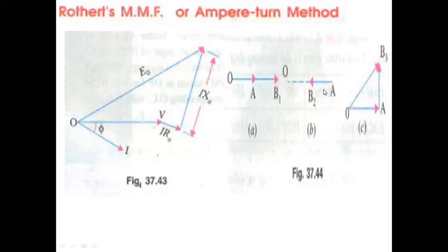Okay, so here OB2 is required to produce full load current on the short circuit. If power factor is unity, the armature reaction is cross magnetization. That is, the effect is only distortion. So the field ampere turns required is OB3. This is for lagging, this is for leading, and this is for unity power factor, OB3.